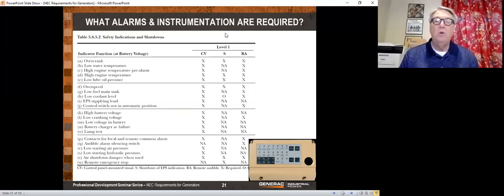So now look at this. You've got to have an overcrank, you've got to have low water temperature, you've got to have a high engine temperature pre-alarm, high engine temperature, low lube oil pressure, overspeed, low fuel main tank, and so on and so forth. The left column over here says control panel visual. That's basically the controller on the generator. The S stands for shutdown, so they're saying overcrank you need to shut down, but low water temperature you don't. And then over here is your remote annunciator or your remote audible. And in the lower right-hand corner is a remote annunciator.